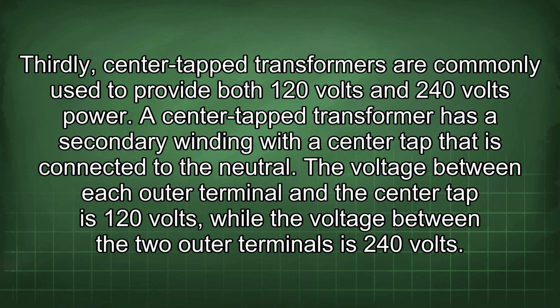A center tap transformer has a secondary winding with a center tap that is connected to the neutral. The voltage between each outer terminal and the center tap is 120 volts, while the voltage between the two outer terminals is 240 volts.